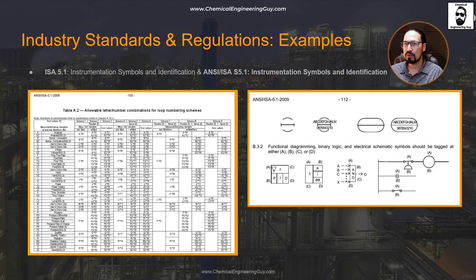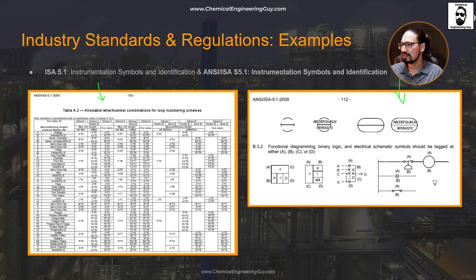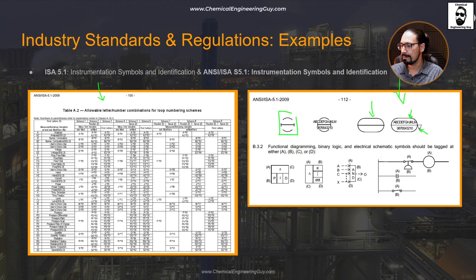This is the ISA 5.1 standard. You can see here the first combination for loop numbering, and these types of standards show how to use the nomenclature. This is a diagram you're going to see a lot — these types of tags. Remember, letters go on top and numbers go on the bottom.